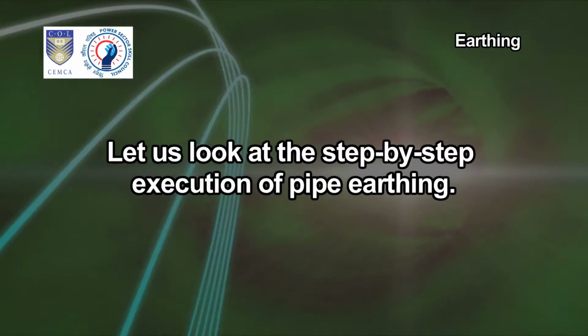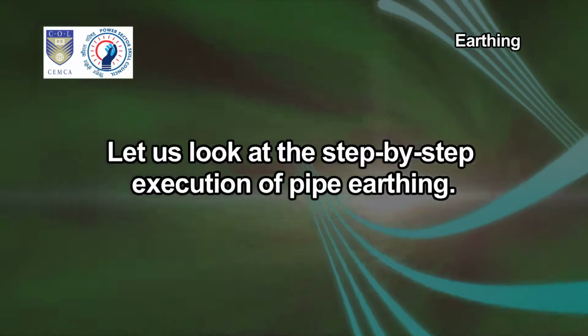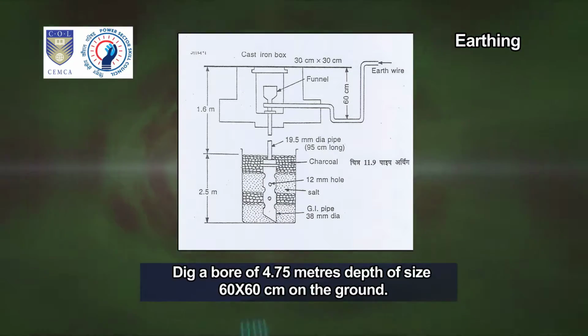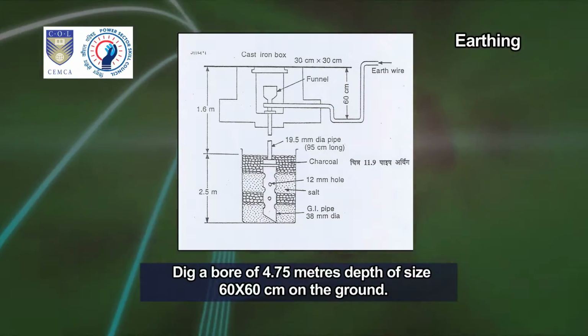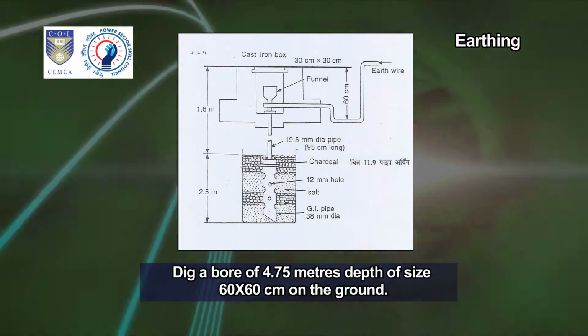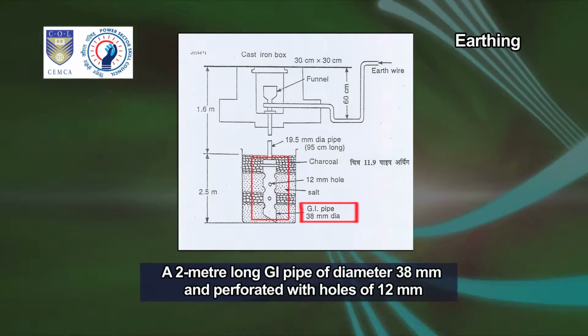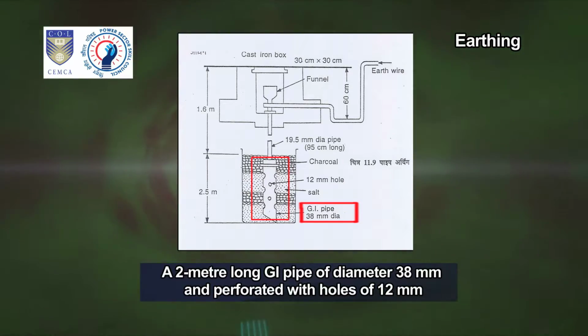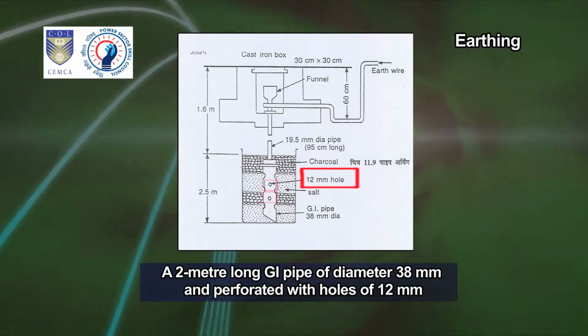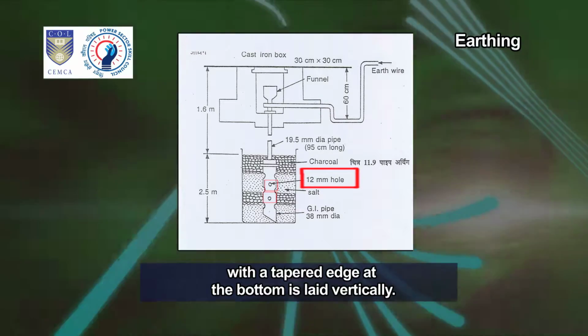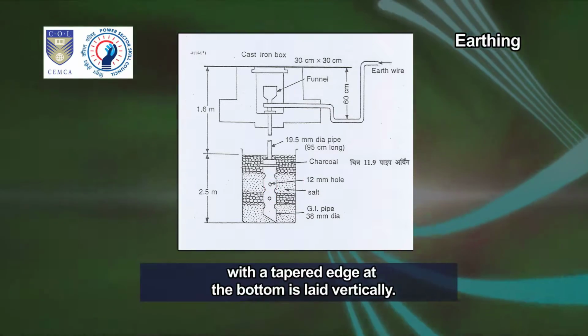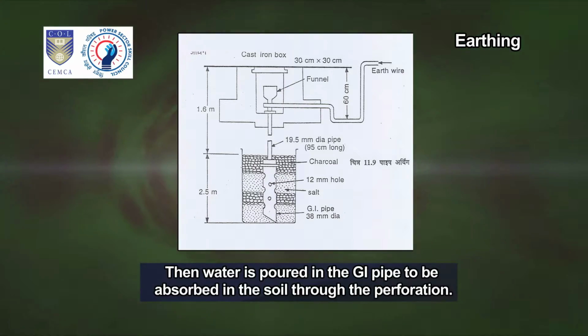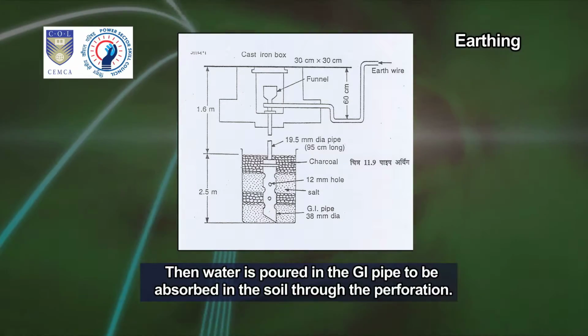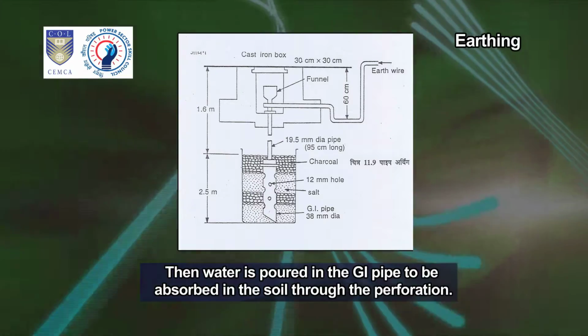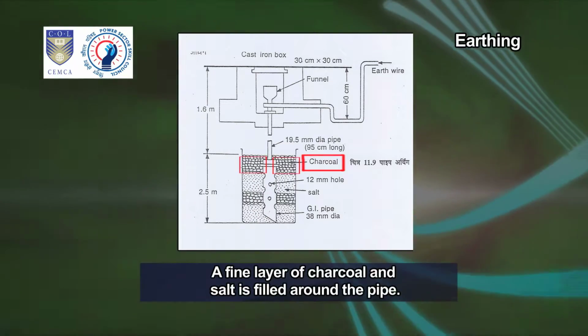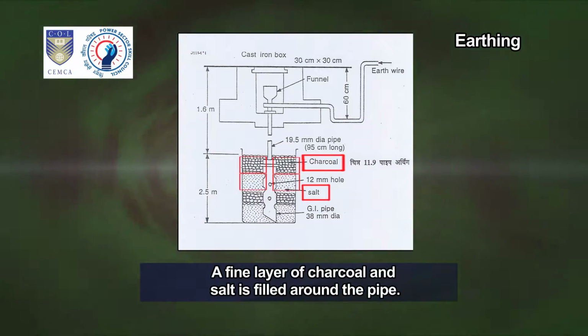Let us look at the step-by-step execution of pipe earthing. Dig a bore of 4.75 meters depth of size 60 by 60 centimeters on the ground. A 2 meter long GI pipe of diameter 38 mm, perforated with holes of 12 mm with a tapered edge at the bottom, is laid vertically. Then water is poured in the GI pipe to be absorbed in the soil through the perforation. A fine layer of charcoal and salt is filled around the pipe.